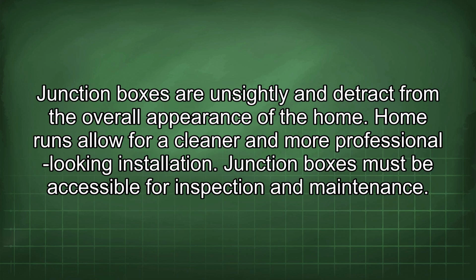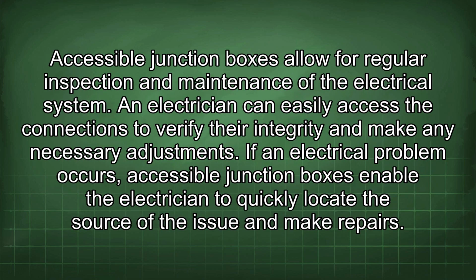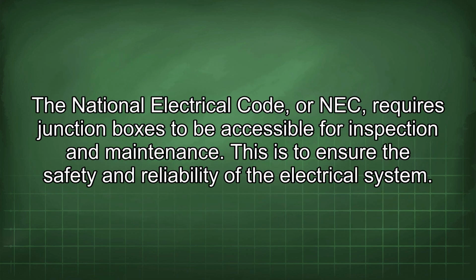Junction boxes must be accessible for inspection and maintenance. Accessible junction boxes allow for regular inspection and maintenance of the electrical system. An electrician can easily access the connections to verify their integrity and make any necessary adjustments. If an electrical problem occurs, accessible junction boxes enable the electrician to quickly locate the source of the issue and make repairs. The National Electrical Code, or NEC, requires junction boxes to be accessible for inspection and maintenance. This is to ensure the safety and reliability of the electrical system.